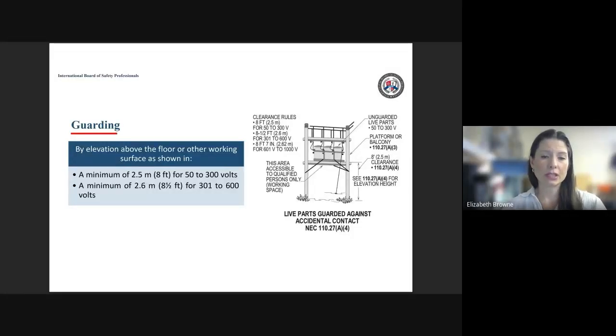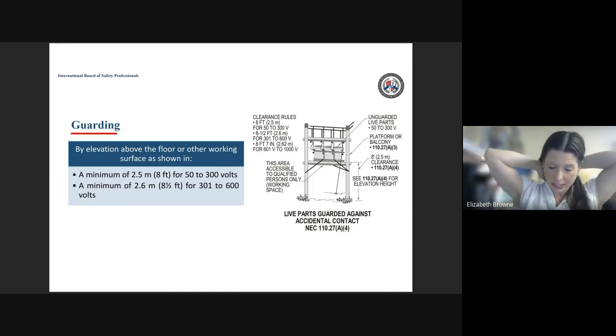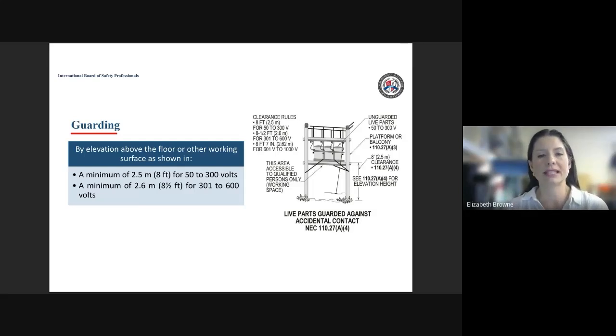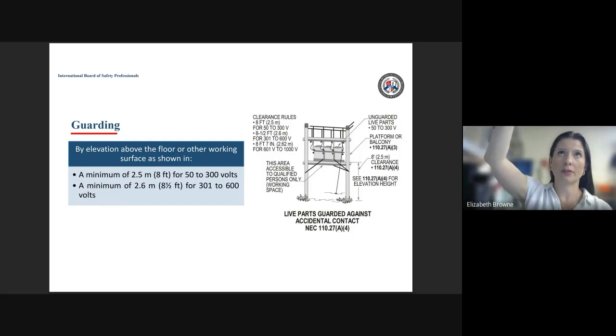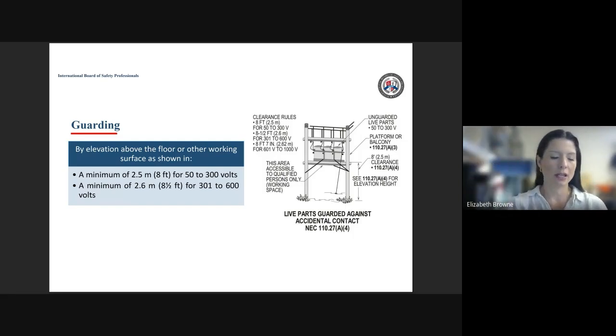All right, so by elevation, we talked about a minimum of 8 feet for 50 to 300 volts and 8.5 feet for any voltage over 300 to 600 volts. These can be live and unguarded in any other way, but just by distance or by elevation. So those are the clearance rules there. And I've had an OSHA inspector get a measuring tape out and measure at a facility that had some live electrical equipment up on the ceiling and make sure that it reached that clearance rule.